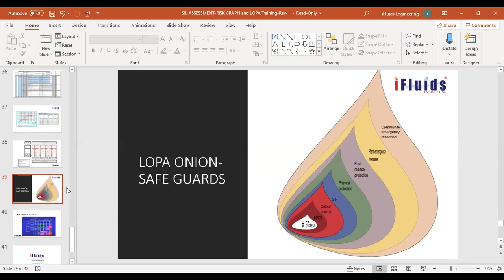Okay, Mr. Suresh, I think regarding this proof test, you need to make a shutdown, or you need to make some kind of override signal for the input. Yes. How can you test the final element itself? You have one loop. That is the problem. That is what we risk professionals will tell you: add an additional protection layer. Suppose you have one single transmitter, one logic solver, one XV. If it is a SIL3, you will not be able to check it. Closing the XV is not possible.